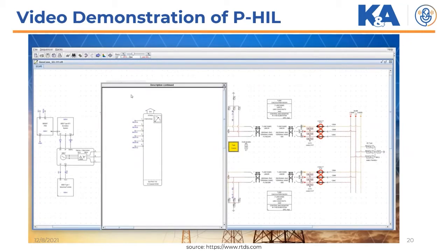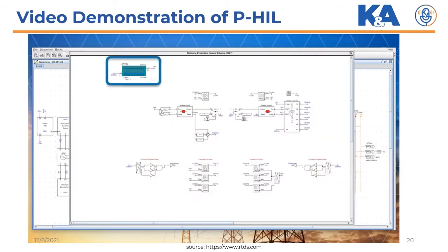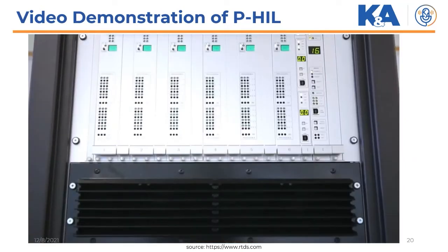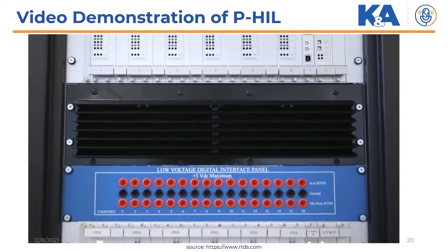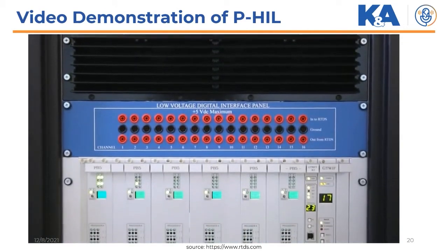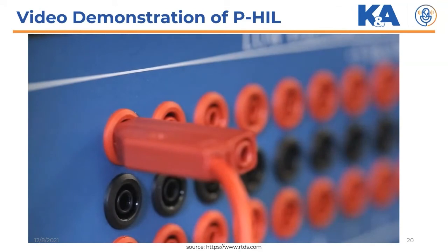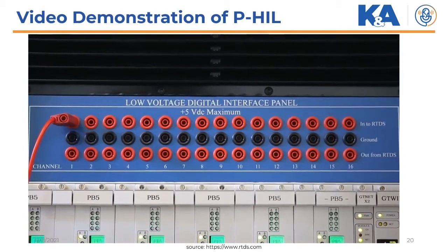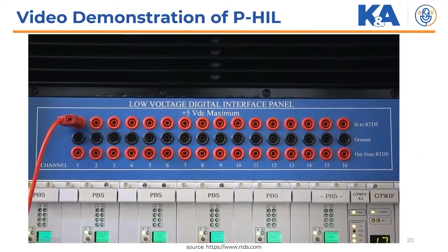The digital to analog conversion is carried out by the RTDS simulator's GTAO card. In this case, the burden currents and voltages from the CTs and CVTs are the outputs. The front panel interface component is used to provide a digital interface to the relay. It defines signals to be communicated via the digital input and output panel mounted in the RTDS simulator cubicle. Here, the output contacts from the physical relay are used as input signals to control the software breaker.